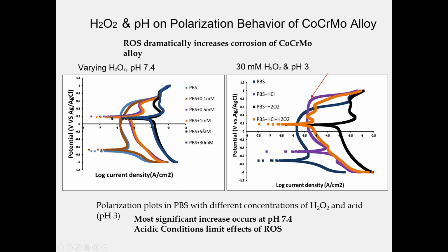we see that with increasing concentrations of hydrogen peroxide from 0 to 30 millimolar, we get a very profound shift in the corrosion behavior of cobalt chromium, where the corrosion currents rise about 40 times just by the presence of these reactive oxygen species up to about 30 millimolar. Indeed, at 5 millimolar, we're seeing as much of an effect as at 30 millimolar. Interestingly, when you go to a lower pH, so this black line on the right curve represents pH 7.4, and when we adjust the pH down to pH 3, we are suppressing the corrosion in the presence of hydrogen peroxide. So acidified hydrogen peroxide containing solutions are not as severe on cobalt chromium as pH 7.4 hydrogen peroxide solutions. So physiological pHs can induce much more significant corrosion of these alloys when ROS species are present.